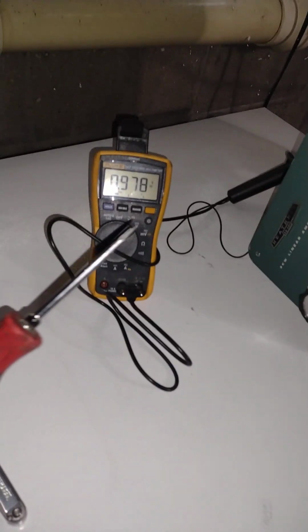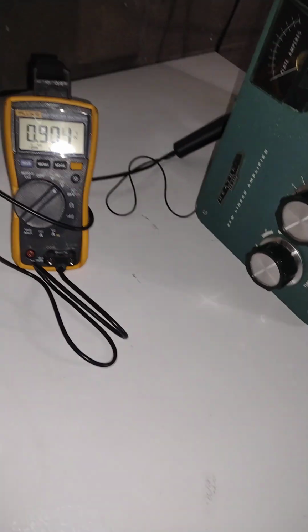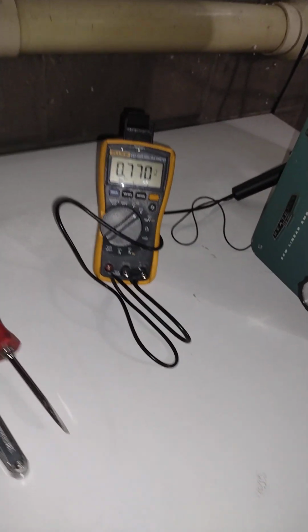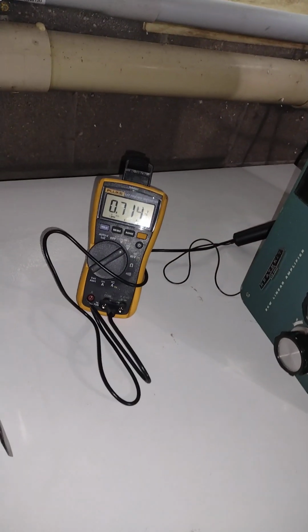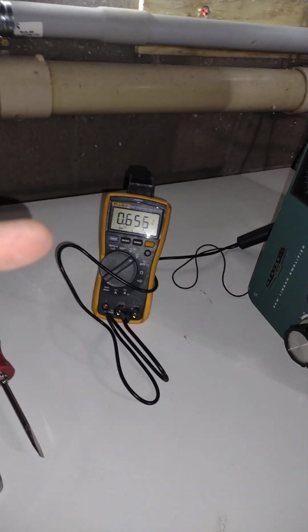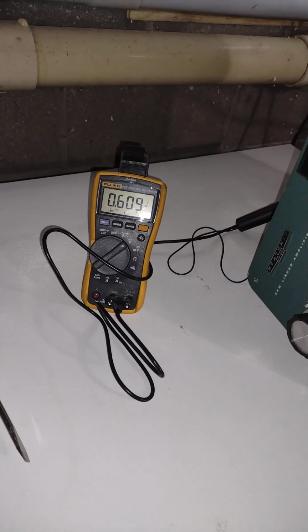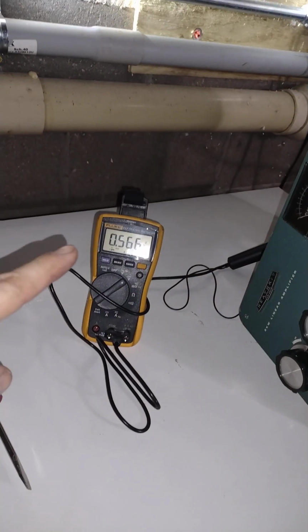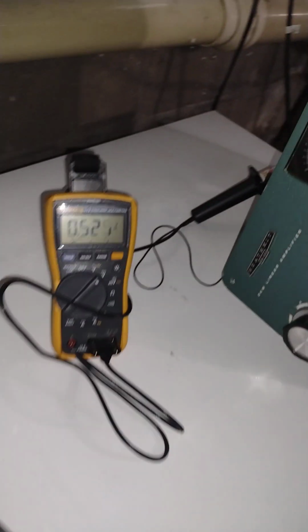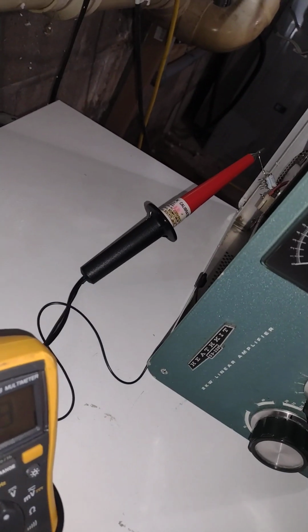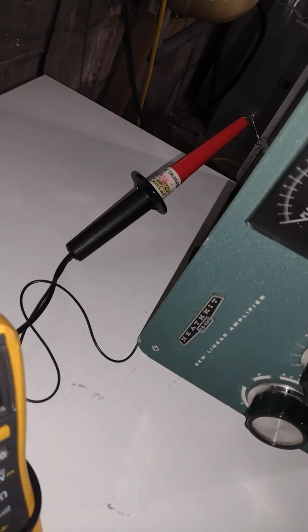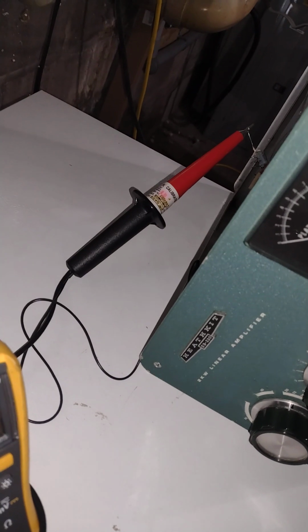Put the glove on, short it to ground, hold it there for a little bit. I'm not waiting 30 minutes, ain't nobody got time for that. Right now, 0.7 volts is still 700 volts—every 1 volt is 1,000 with that probe. At one point it was calibrated, so that means something to someone, or it means nothing to a lot of people.